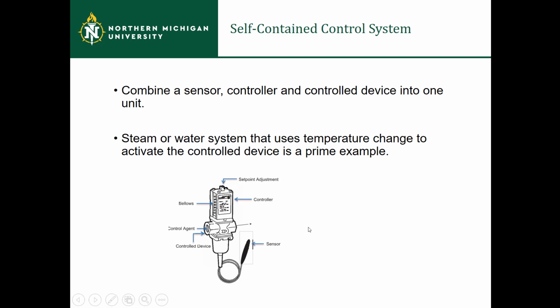Your self-contained one basically combines a sensor, controller, and control device into one unit. Here's an example right here. A steam or water system that uses temperature change to activate a control device is a prime example. So we have a little sensor here, the control device inside, and the controller up at the top here with a set point adjustment. If that water system is getting too hot or too cold, for instance, the sensor changes based on the temperature, and it kicks on what our adjustment and set point is to say I need a little bit more heat, or I need a little bit less heat within my system.